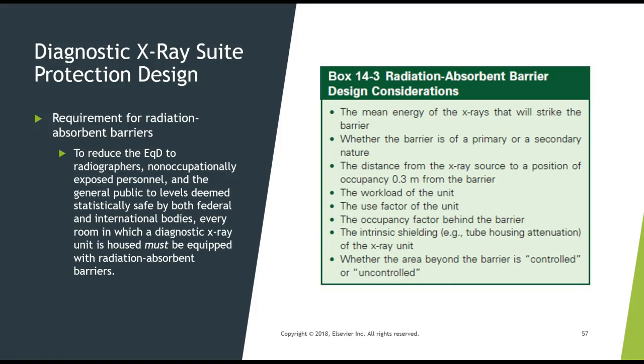And the barrier considerations that they take into mind when they build these rooms and come up with these guidelines are the kVp, which is the mean energy of the X-rays that are going to strike the barrier, if it's going to be a primary or secondary wall, and the workload and the use factor and the occupancy factor for that area.